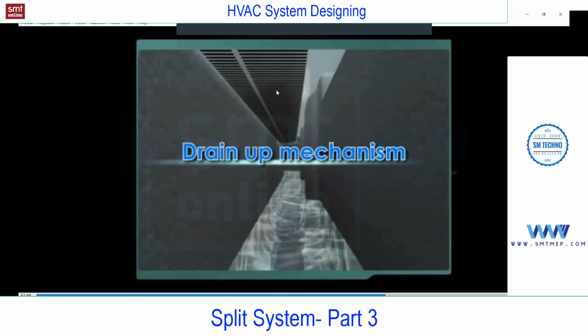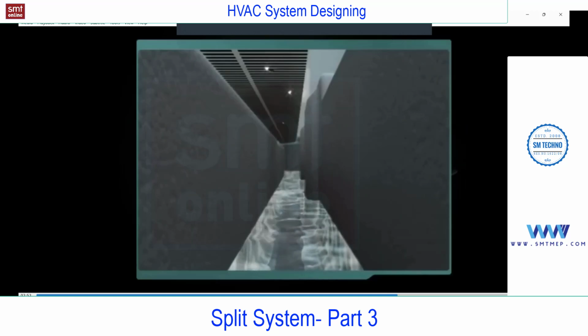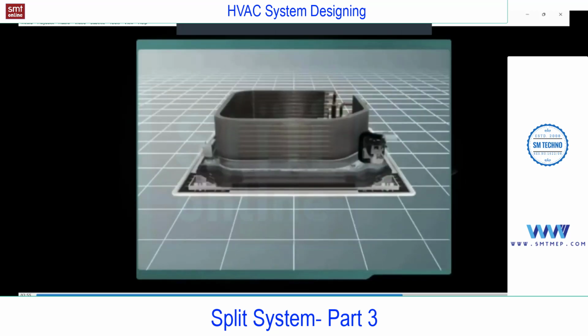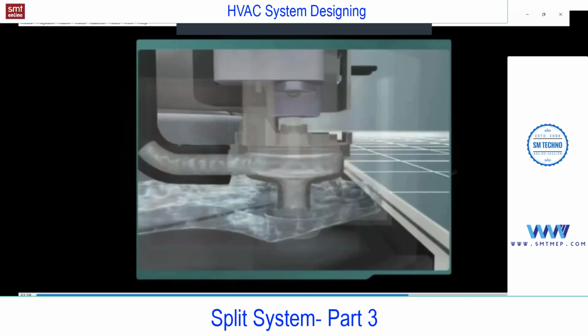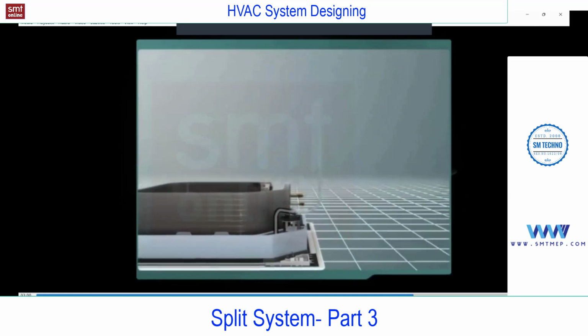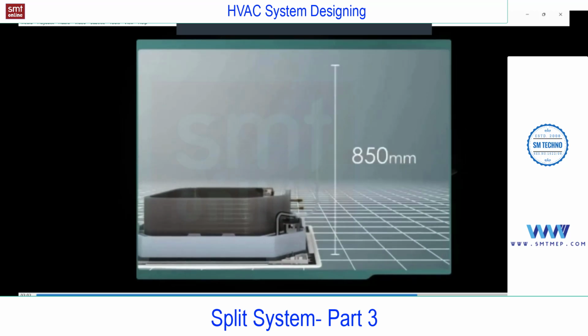You see above this evaporative coil and below the collection of water. This is a drain tray. You see in this model, we can connect the drain pipe 850 mm above this unit. And this may vary from vendor to vendor, make to make, but definitely you'll find the drain pump in all the cassette, and one can connect the drain pipe above this unit level.